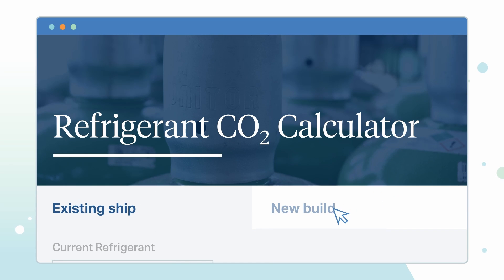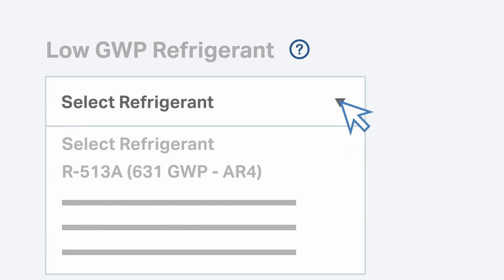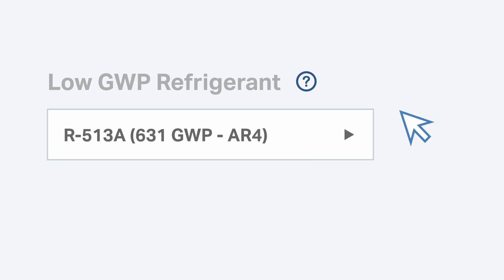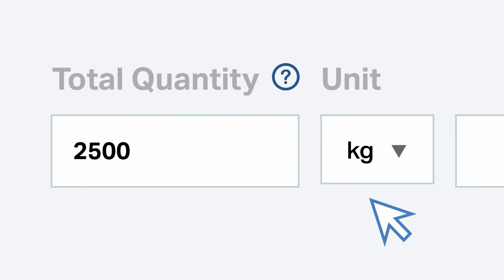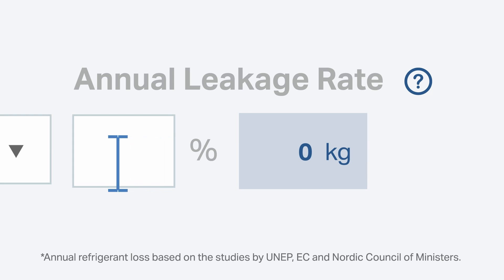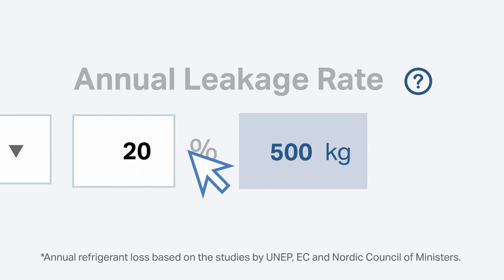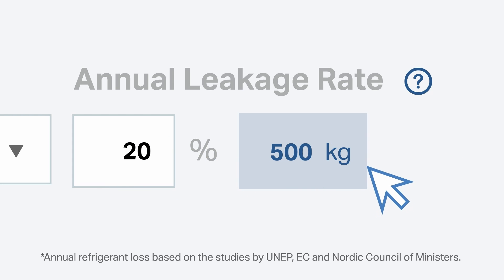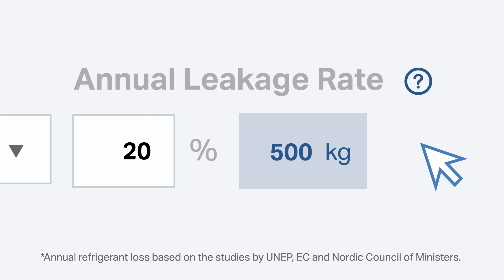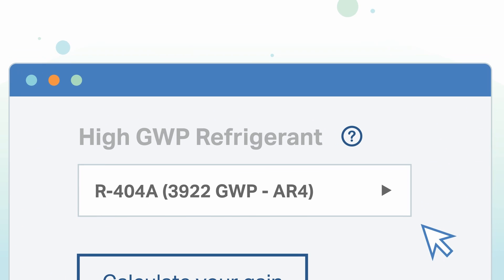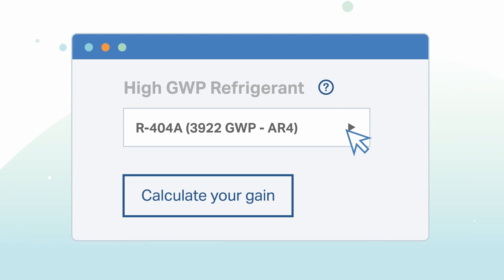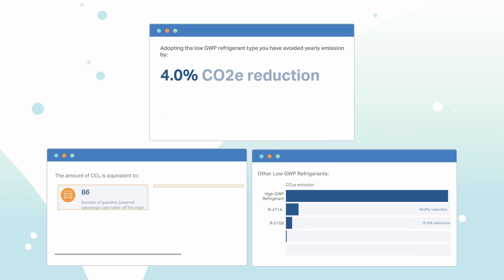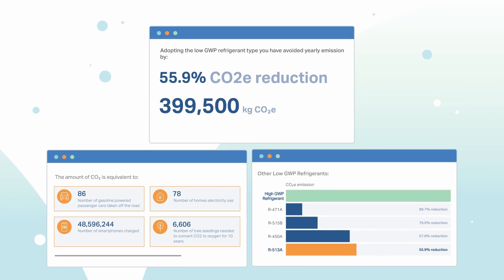For new build vessels, start by choosing the low GWP refrigerant from the drop-down menu. Key in the total amount of refrigerant charge in the system. Enter your annual leakage rate or use the typical rates as determined by studies conducted by UNEP, EC, and Nordic Council of Ministers. Our calculator will automatically shortlist a high GWP refrigerant for comparison. Then calculate the difference — you can see the amount of CO2 avoided by adopting a lower GWP.